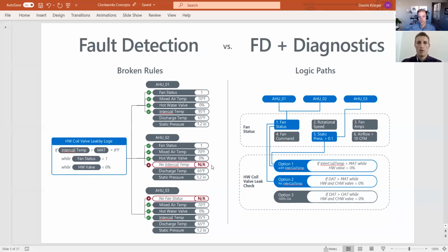One of the challenges with the custom rule approach is that it relies on matching point types. So if I've built a rule to detect a leaking hot water coil valve using preheat discharge temp, mixed air temp, fan status, and hot water valve, I'm looking to match those conditions across every piece of equipment where I might want to detect the same thing.